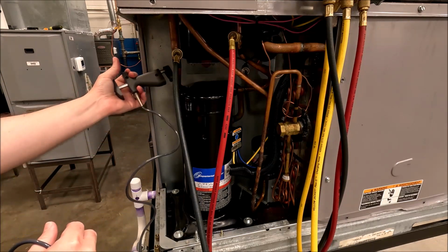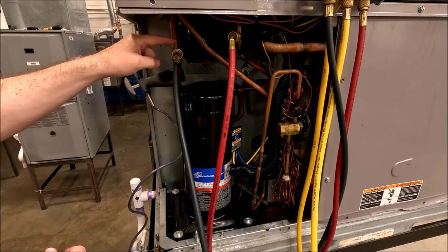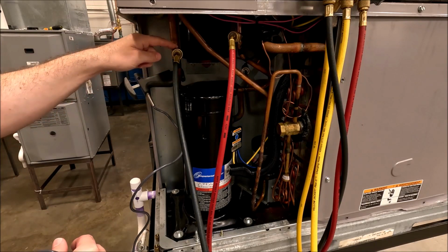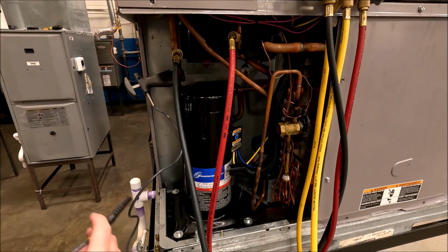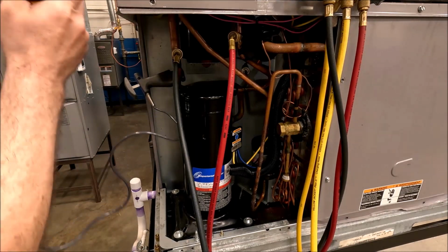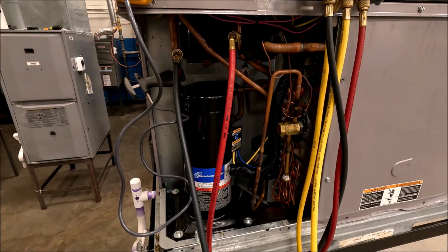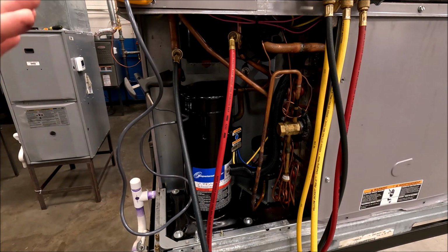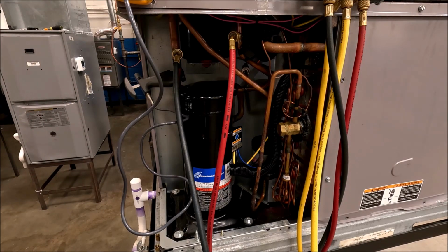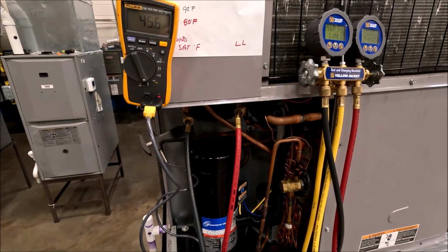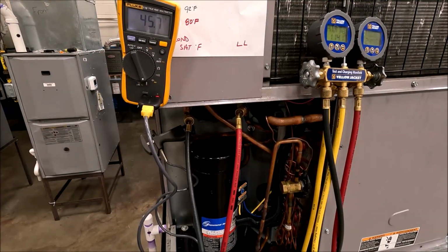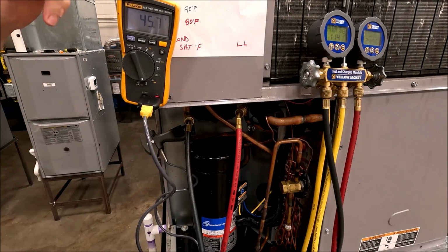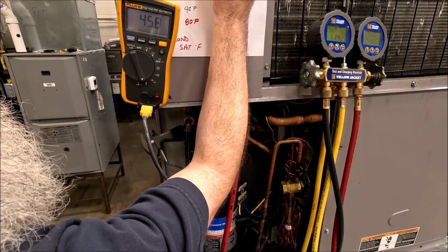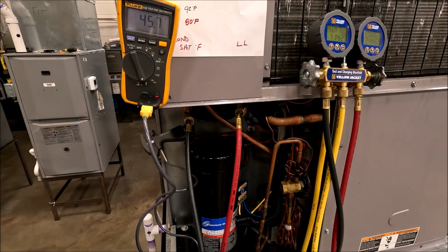So I'm gonna use my pipe clamp here and check that. It just happens to be the same line where I've got my low pressure gauge hooked up. So I'm gonna put that there. I'm gonna bring my Fluke meter over here, and I'm gonna check this particular line. Even though it's off screen a little bit, might as well show you already. You can see up here, I've got a 34.5 degree coil or so, and I've got a 45 degree line. So my vapor line right here is 45 degrees, almost 46, okay?